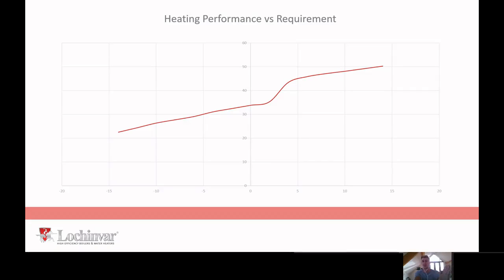So if you were to look at any manufacturer's air source heat pump, the data will be published as standard at 7 degrees centigrade outside air temperature. That's the outside air temperature that apparently is our average in the UK. So for that reason, it's a 45 kilowatt heat pump, but it is only really as good as whatever our design air temperature is. So you're in the city of London, chances are you're going to be designing to -2. If you're somewhere more rural, maybe you're coming in from East Anglia or something, you might be designing to -4 if that's where the site is.